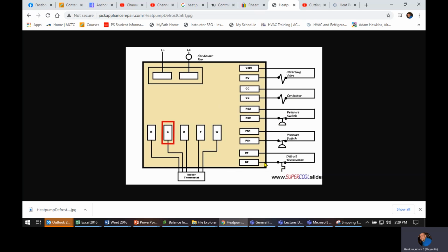Then you've got this little doohickey down here, this little defrost thermostat. And this thermostat is, actually, okay, the way you're looking at this, it's kind of backwards. It is a break on rise, make on drop. So it is a heating thermostat, essentially. It's sensing when the temperature gets to a certain low temp, and then it's energizing.